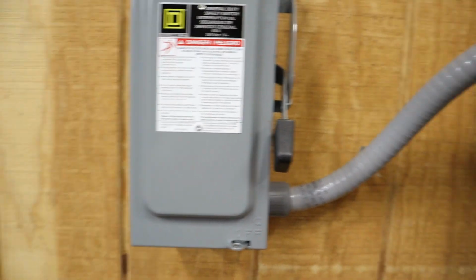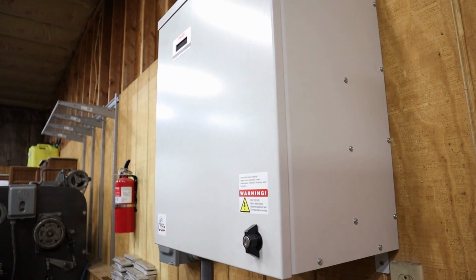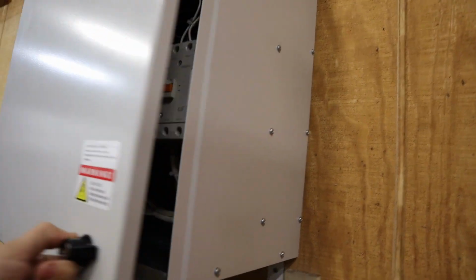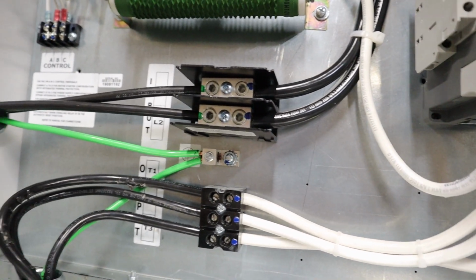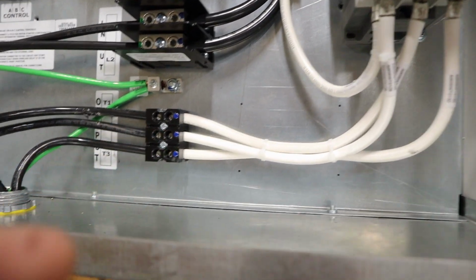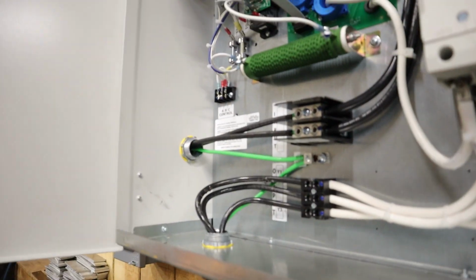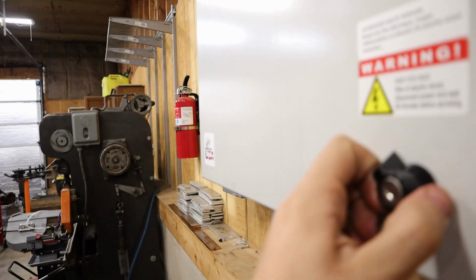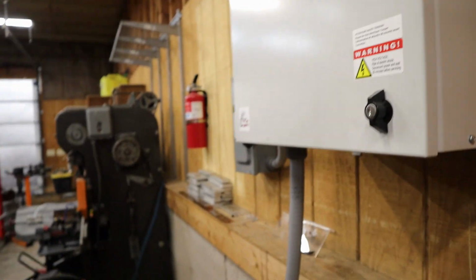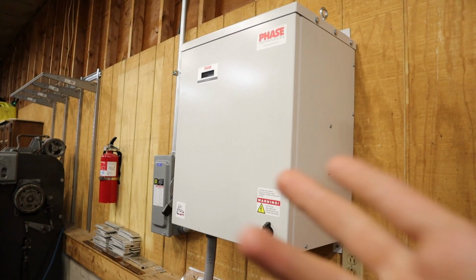Then the two hots go up, and the ground too, into a Phase Perfect PT355 with the digital readout. The two hots and the ground get bonded together, and you can see a manufactured third leg comes out on T3. Super easy to wire if you were worried about doing one yourself. But my problem is, here, hold on. When you have this loaded up, it'll give your input power. Currently, I have basically 230 volts coming in from the street, from the overhead lines transformer. Everybody typically shares a transformer. My arm's getting tired.